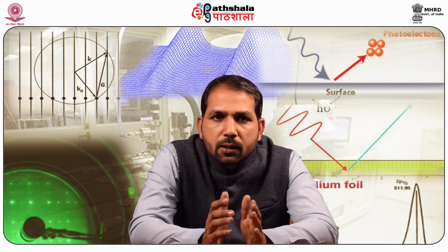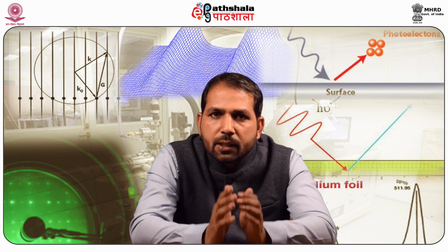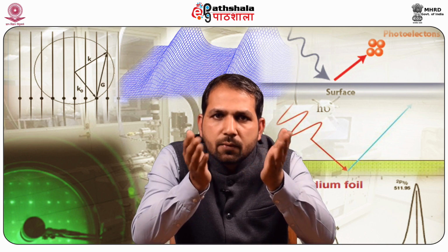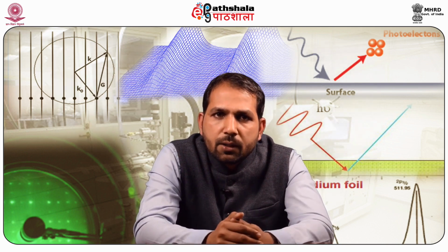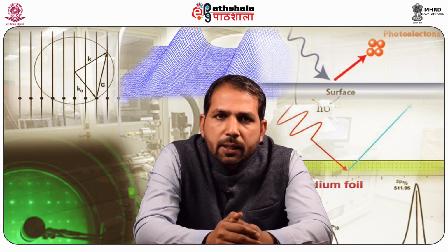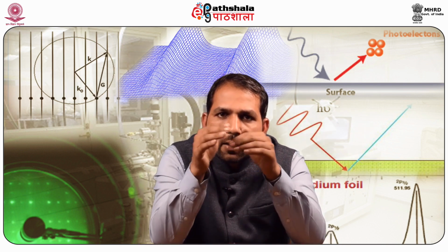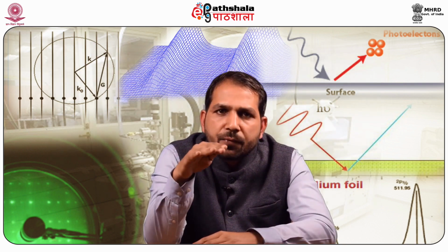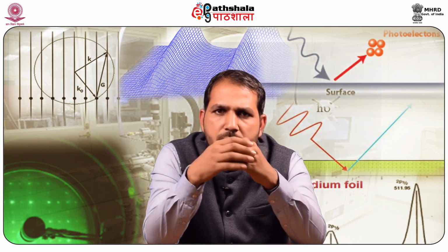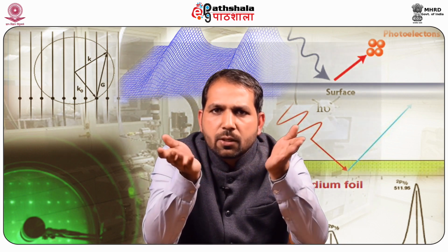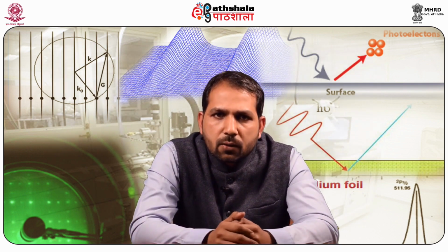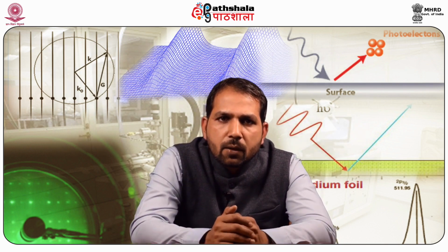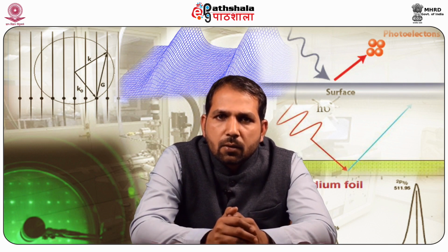An electron gun consists of a heated cathode and a set of focusing lenses which sends the electrons with energy between 20 to 300 electron volts. As the electrons collide with the surface of the sample, they diffract in numerous directions depending on the surface crystallography. Once the electrons diffract, they head back towards three grids, followed by a phosphor covered screen.